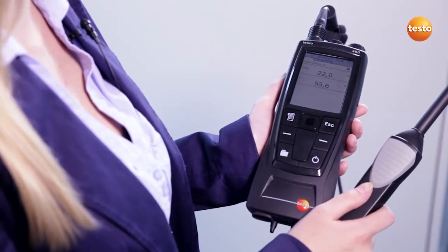of the room climate. In order to be able to judge whether the ambient conditions are actually causing the thermal discomfort, I'll now conduct a PMV/PPD measurement. The objective of the measurement is to obtain an overall objective evaluation of the climatic conditions in the room. In addition to the classification of the room as too warm or too cold, I obtain a percentage of people who are dissatisfied with the ambient climate.